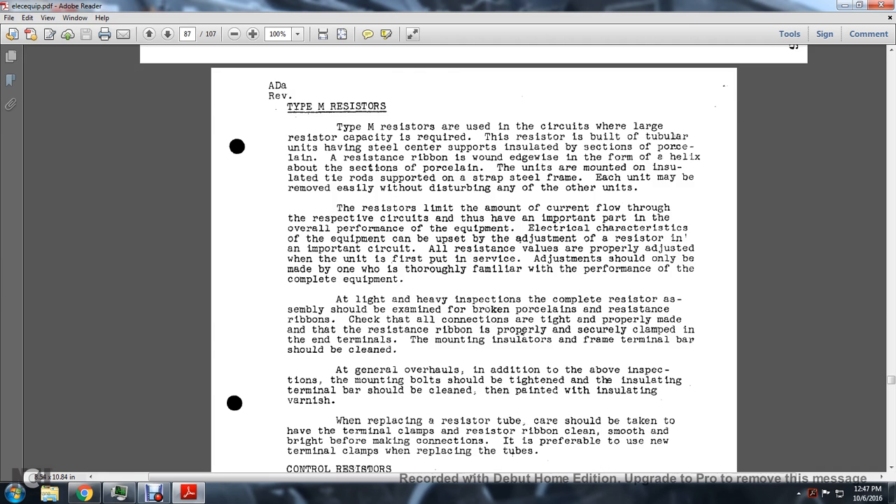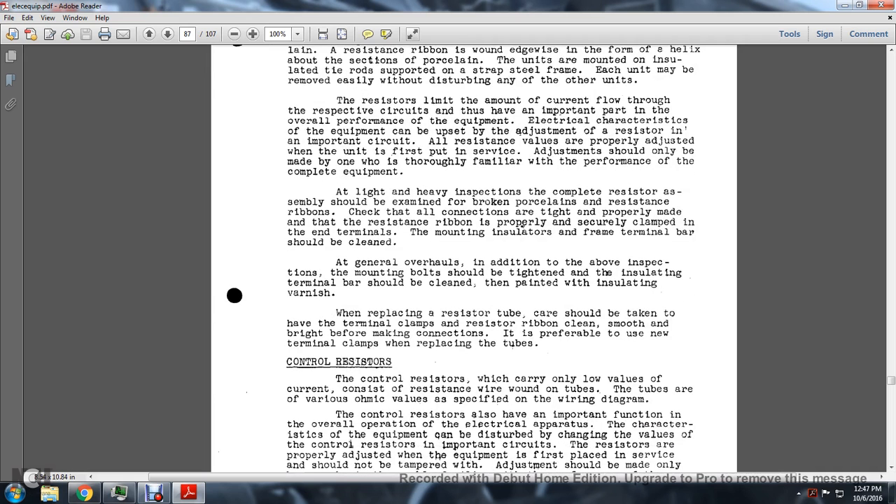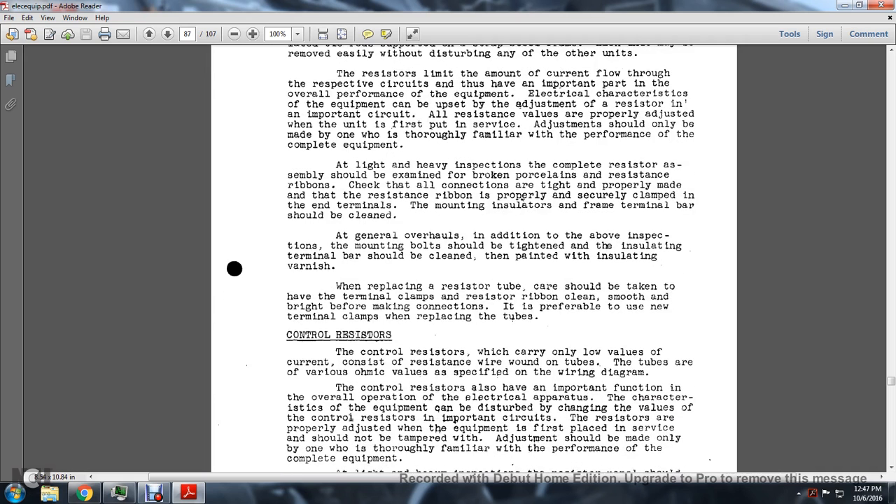All resistance values are properly adjusted when the unit is first put in service; further adjustment should only be made by someone thoroughly familiar with the performance of the complete equipment. At light and heavy inspection, resistors should be examined for broken porcelain or resistor ribbons. Check all connections for proper tightness. Resistance ribbons should be securely clamped in the terminals. Terminal bars should be cleaned. At general overhaul, mounting bolts should be tightened and insulation checked. Terminal bars should be cleaned and painted with insulating varnish.